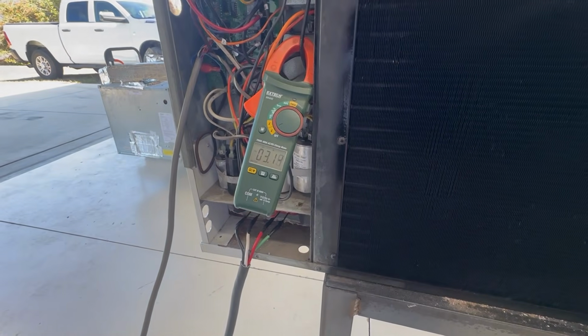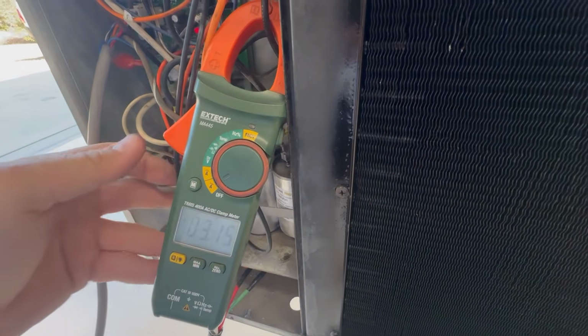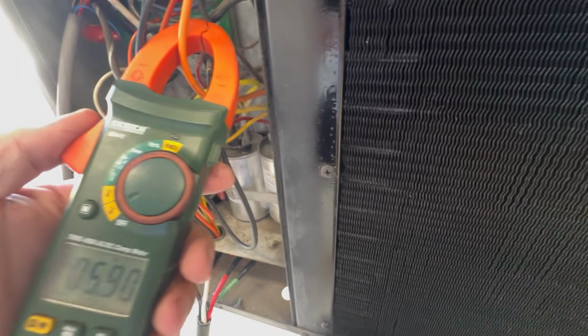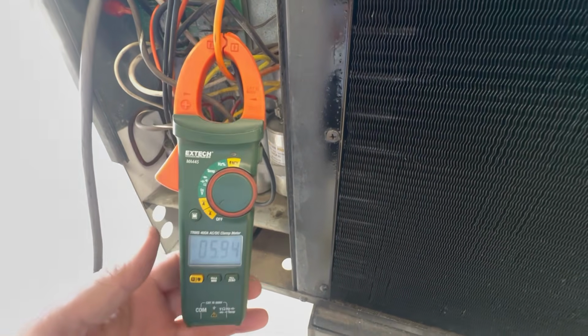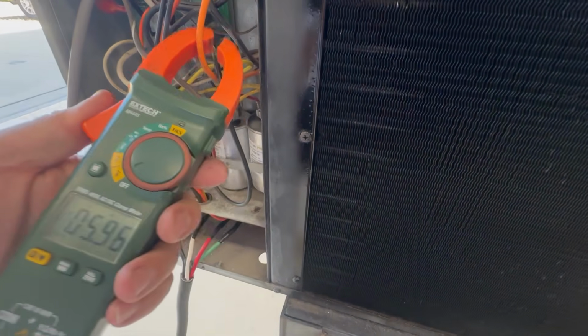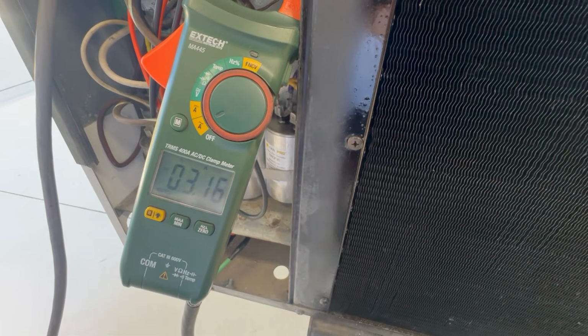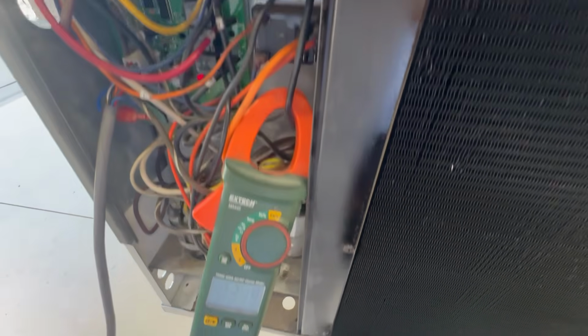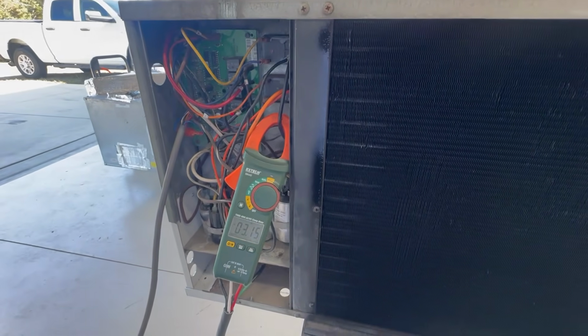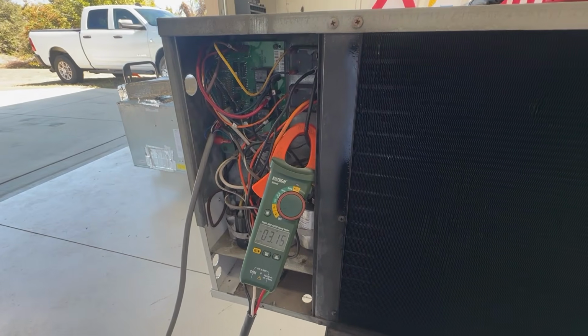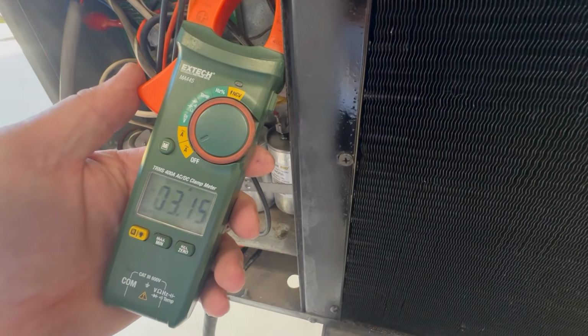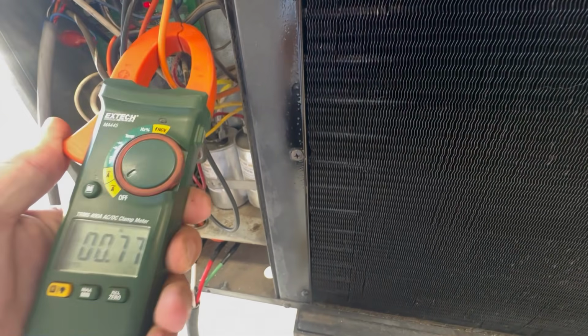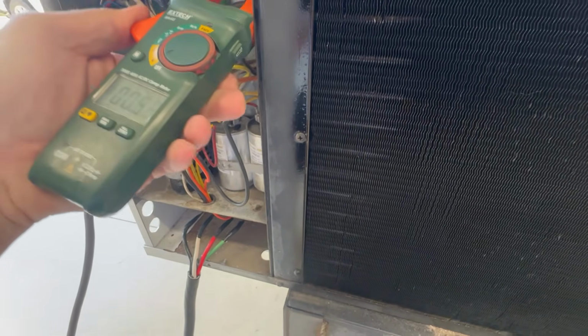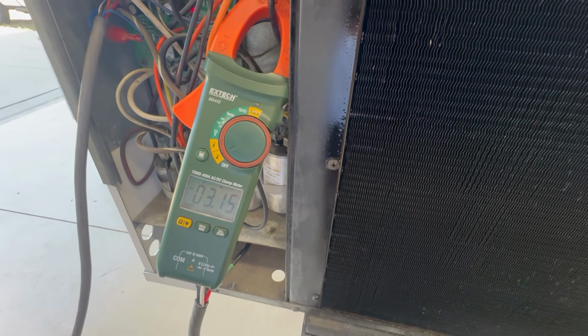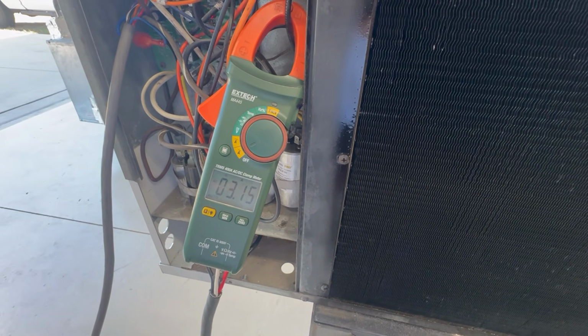It's about 19 degrees, but here's the problem I'm seeing right here. See how this one's got 3.15 and this one's got 592? I can tell you 20 minutes ago those numbers were equal. Now that the compressor has gotten a little bit of heat on it, it has dropped down. You can see what my temperature was in heat pump mode -- I did that first because it's a little cool in the shop today. But the longer this compressor has run, the lower that amp draw has gotten, and I feel like the charge is correct, but we've definitely got a compressor that has gotten hot and is having a problem. So more than likely we've got a compressor problem with this one.